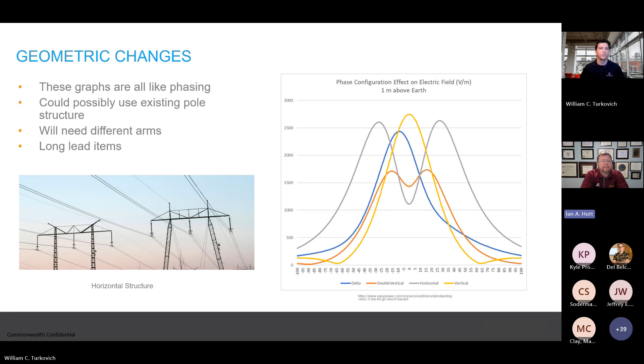Another thing we can talk about is that EMF is a distance squared function. So the farther away we get, the more those electric and magnetic field values drop, and that works for both cases. We always look at the minimum sag heights, and generally those are your worst case. If we know we have pretty strong EMFs that are driving requirements, there's always the solution to possibly go taller. If we can get those sags raised, those towers raised, or if there's a particular landowner or concerned party with a very high value for EMF, sometimes it can be mitigated with structure height changes.